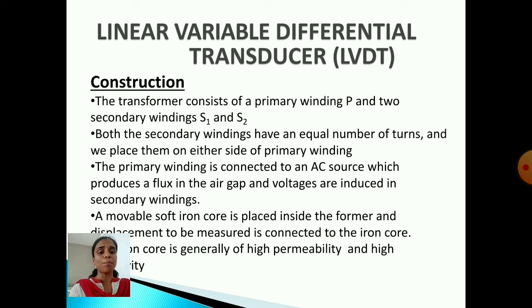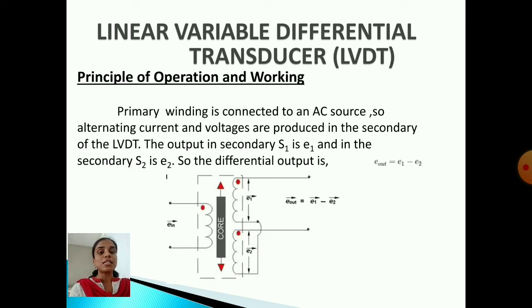A core is placed inside a former and the displacement to be measured is connected to the iron core. It generally has high permeability and high sensitivity characteristics. Now we will see the operation and working. The primary winding is connected to the AC source so that alternating current and voltages are produced in the secondary of the LVDT. The output of the secondary S1 is named E1 and that of the secondary coil S2 is named E2.